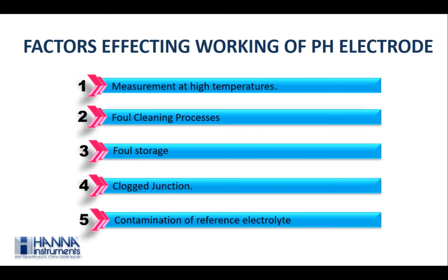Similarly, a clogged junction and faulty cleaning processes go hand in hand. Faulty cleaning or no cleaning practices lead to a clogged junction, leading to sluggish readings and very slow response, as there is no space for the electrolyte to come in contact with the sample, and hence lowering the electrode performance. Contamination of the reference electrolyte solution takes place as the solution being measured is allowed to migrate through the junction, entering the electrolyte cavity, thereby changing its composition and altering the electrochemical reaction completely.